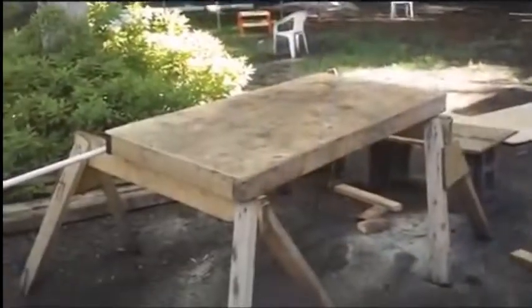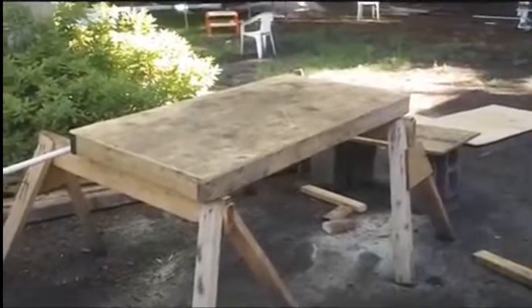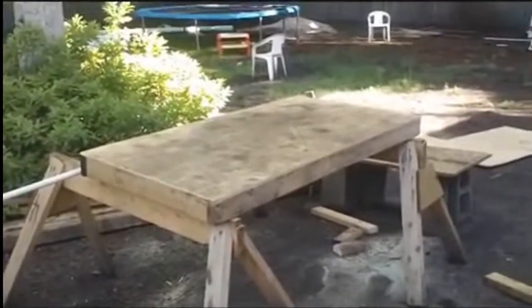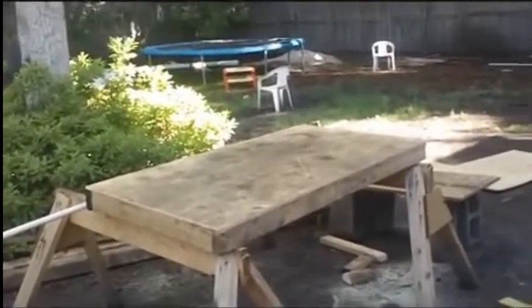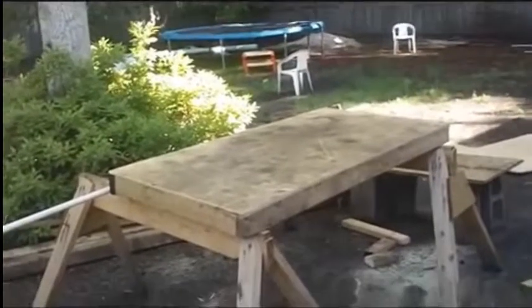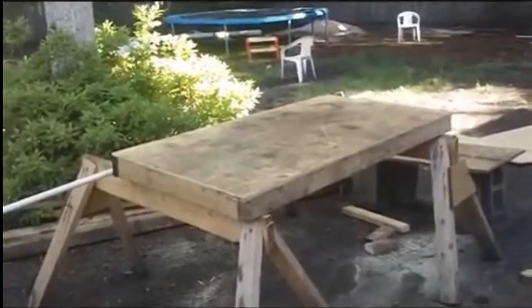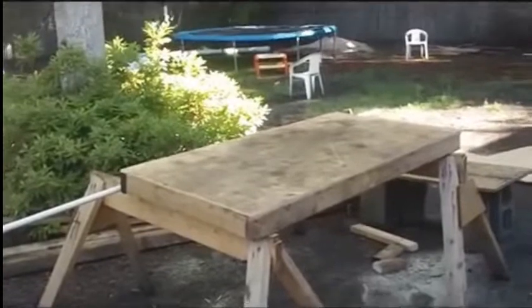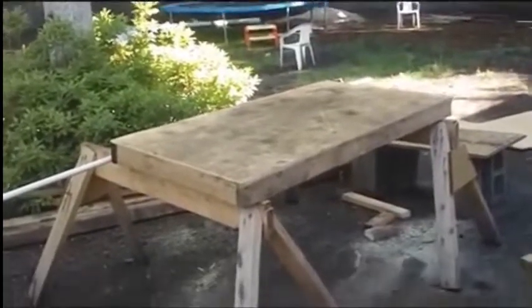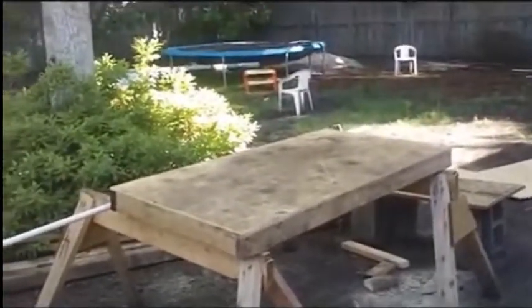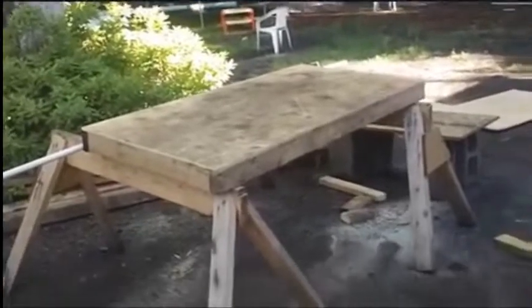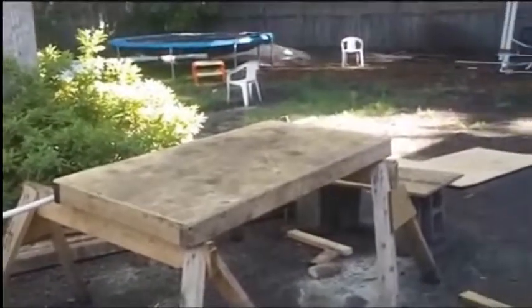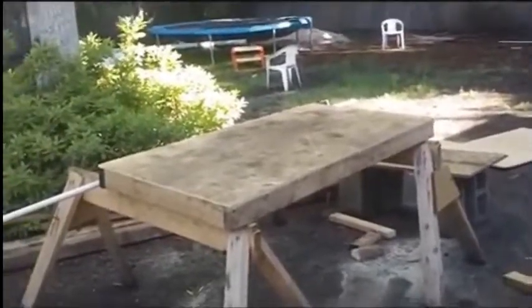Alright, here's our platform I built. It's 32 inches by 60 inches to hold the drain pan and the air handler. I want to boost it up a little bit. We're going to have foam blocks underneath the air handler that will give it about 4 more inches. We got about 4 inches here. That way we know our drain is going to be falling real well. And our secondary drain will have plenty of fall as well, even though it's not as critical. So it'll be all ready. Ari Michael should be here in about half an hour. And I'm about to go pump the old system down.